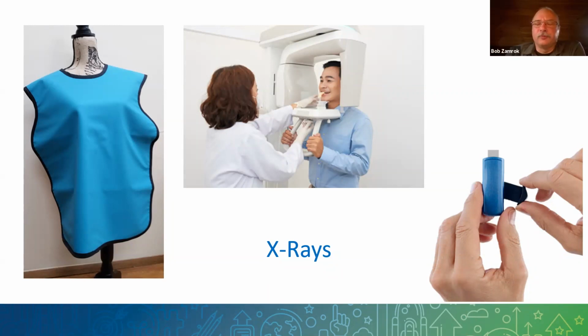I have a love-hate relationship with Cavicide. Tell us more. It is probably one of the best products at killing germs and cleaning equipment. It is also one of the worst products if the concentration's too high or if it's left on too long. It destroys everything. Got it. So for a lead apron, Cavicide would be fine as long as it's used properly, at the proper mix, right? And it's not left on too long. You shouldn't just spray it and leave it. You want to spray it and wipe it off, correct?